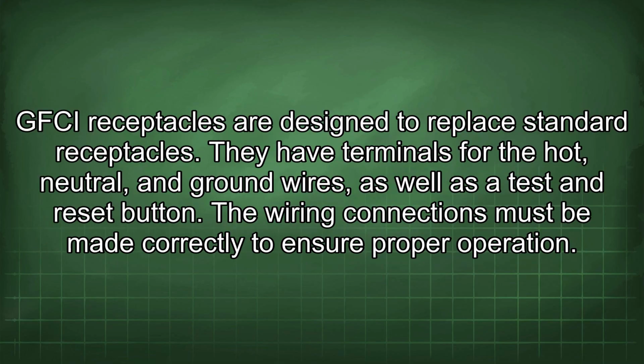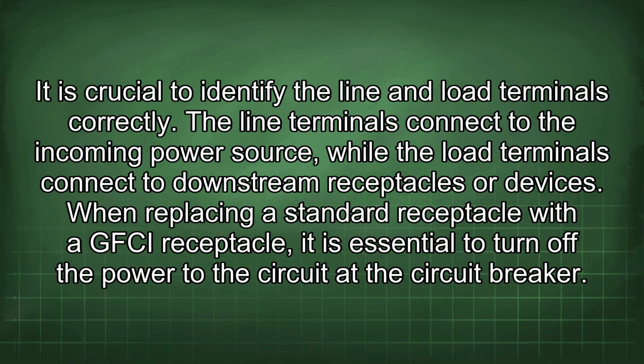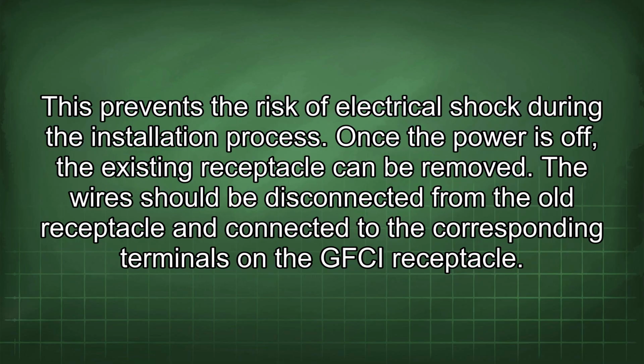The installation of GFCIs is relatively straightforward. GFCI receptacles are designed to replace standard receptacles. They have terminals for the hot, neutral, and ground wires, as well as a test and reset button. The wiring connections must be made correctly to ensure proper operation. It is crucial to identify the line and load terminals correctly. The line terminals connect to the incoming power source, while the load terminals connect to downstream receptacles or devices. When replacing a standard receptacle with a GFCI receptacle, it is essential to turn off the power to the circuit at the circuit breaker. This prevents the risk of electrical shock during the installation process.